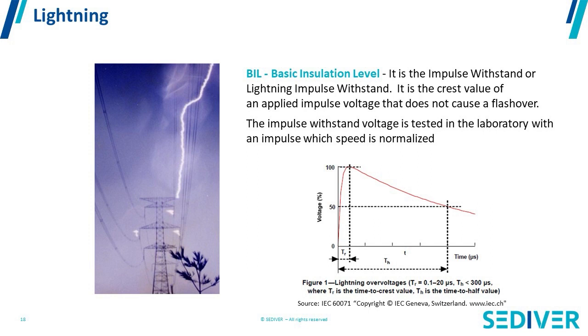Lightning is a phenomenon that is relatively quick, and it is described by the acronym BIL — Basic Insulation Level. The basic insulation level is the impulse withstand voltage: the lightning impulse withstand value that an insulator or insulator string can take. We guarantee these values in our catalogs. When a string designed by an engineering company consists of insulators multiplied 20 to 25 times, it must be capable of withstanding a certain value or have a flashover value defined by the manufacturer.